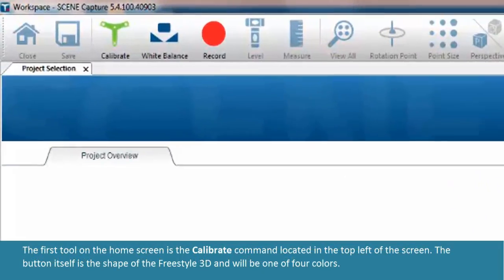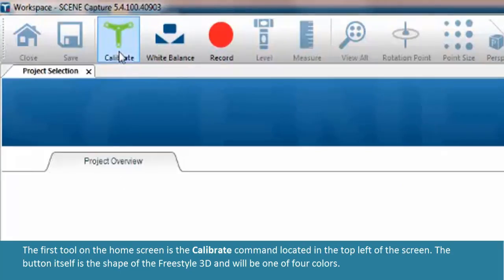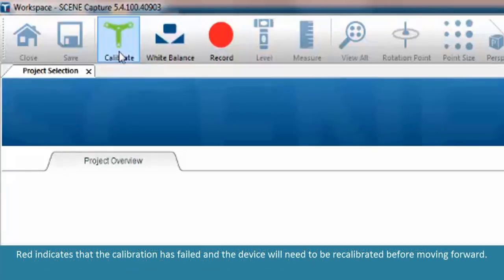The first tool on the home screen is the calibrate command located in the top left of the screen. The button itself is the shape of the Freestyle 3D and will be one of four colors. Red indicates that the calibration has failed and the device will need to be recalibrated before moving forward.